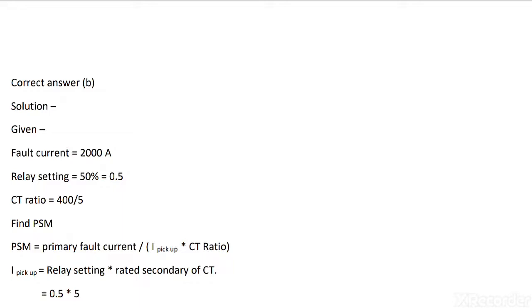PSM means plug setting multiplier. The formula for plug setting multiplier is PSM equals primary fault current divided by I pickup into CT ratio.